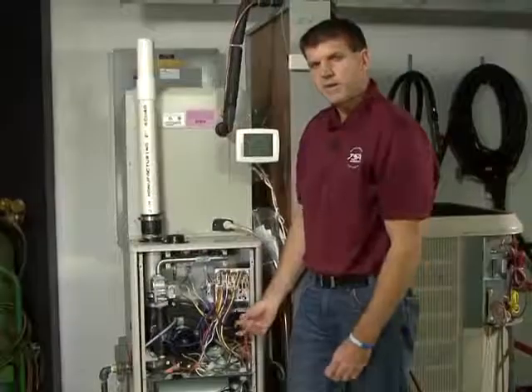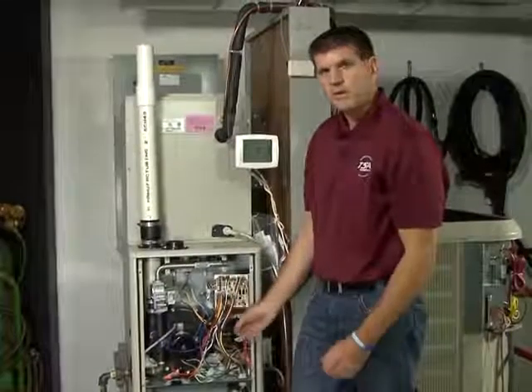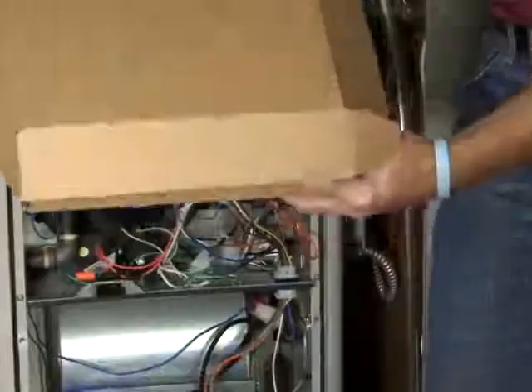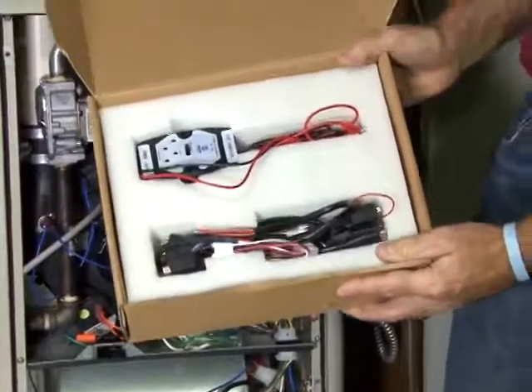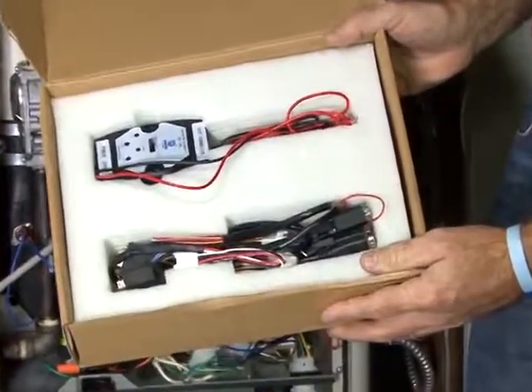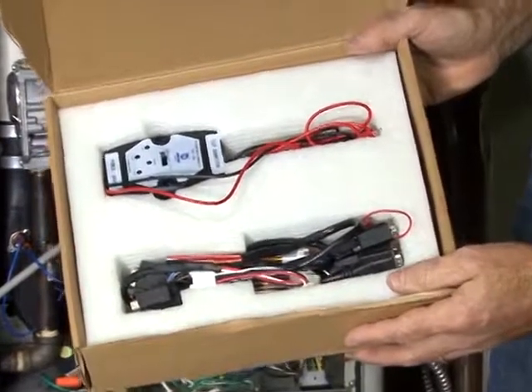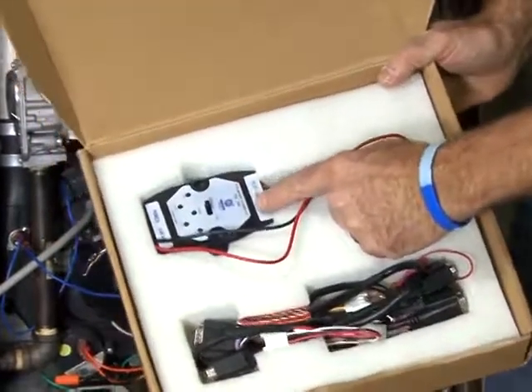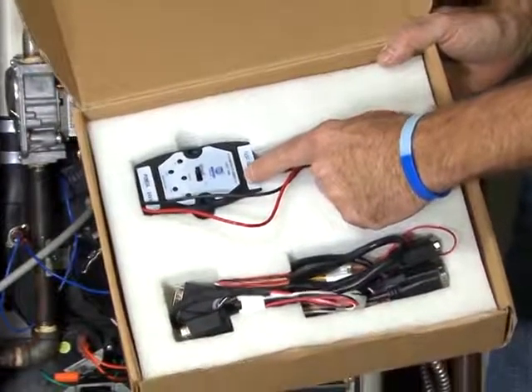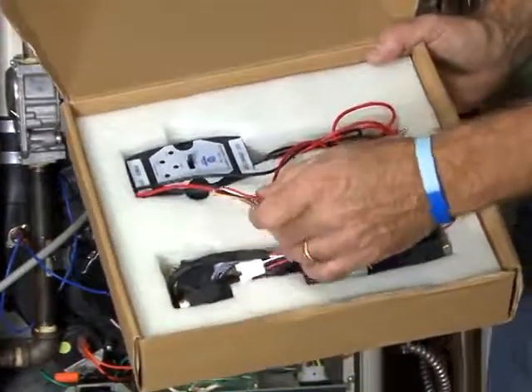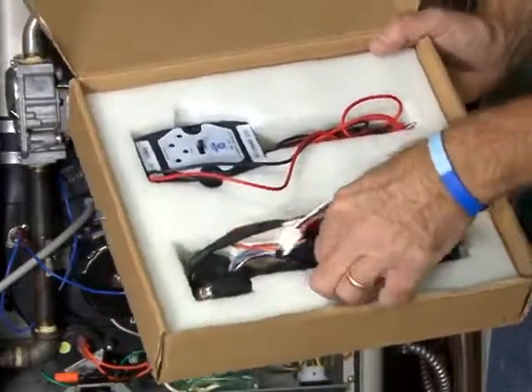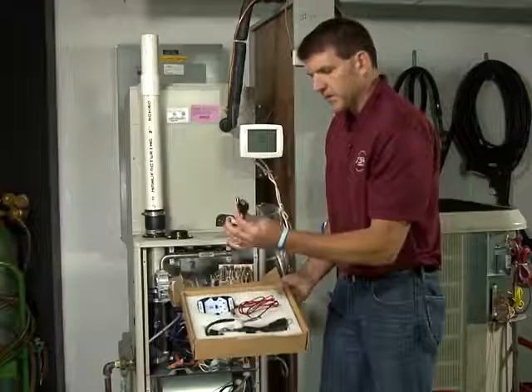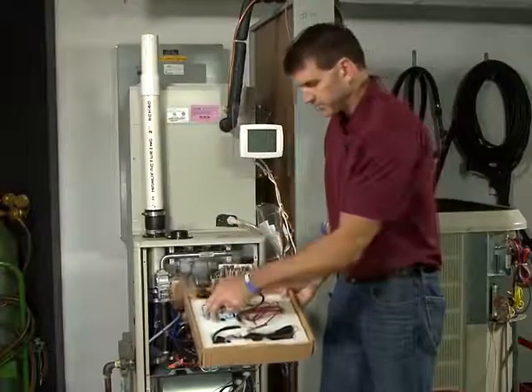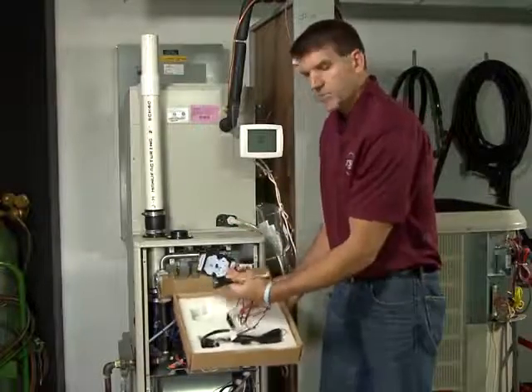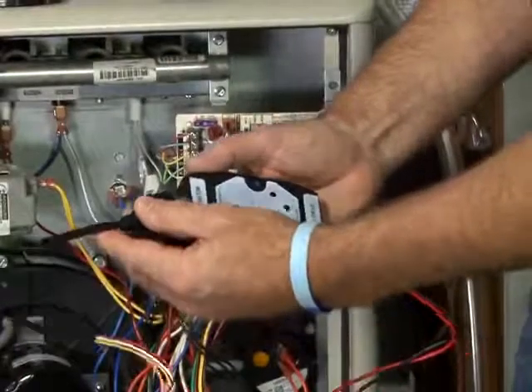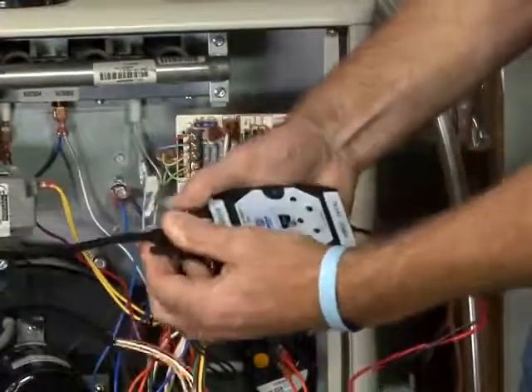The only true way to tell if it's in the motor or the board is with the use of a broad ocean motor tester. With the broad ocean motor tester, we can isolate the motor from the furnace and operate the motor independently through the motor tester. The broad ocean motor tester will come with several different adaptable plugs to attach to whatever motor we're troubleshooting. You'll simply pick your adaptable plug that matches your motor and connect that plug to the broad ocean motor tester.